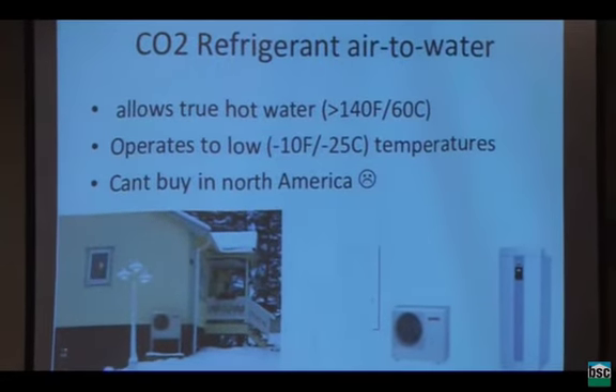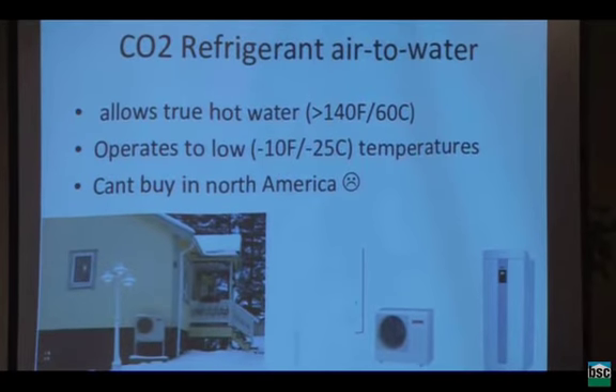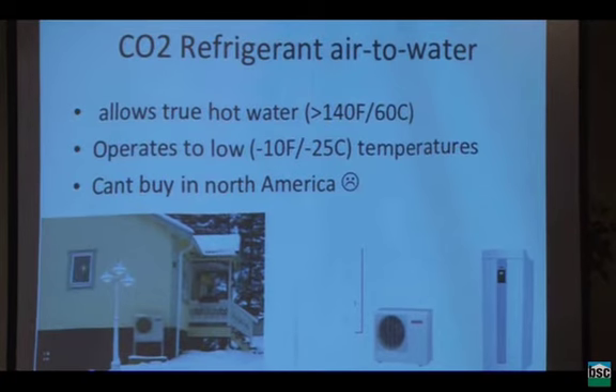Most of the products find no need to rate lower, but in the lab they can do this down to -40 and they still work because it's CO2. And again, you can't buy it here. So this is a Swedish house in the lower left, an outdoor CO2 unit. Notice it's standing up high on stilts so that the snow won't block it when the snow piles up. 4.5 kilowatt unit, which works out to a rated load of about 15,000 BTUs an hour, but it's variable capacity, so she can dial right back down to 4,000 BTUs, up to 15, 16,000 BTUs as needed. And the indoor unit is basically you attach your refrigerant lines to it. It has a tank and the controls and some pumps. And you attach to the hot water, or you attach to the radiators, you attach to fan coils, you attach to floors, and it all works.